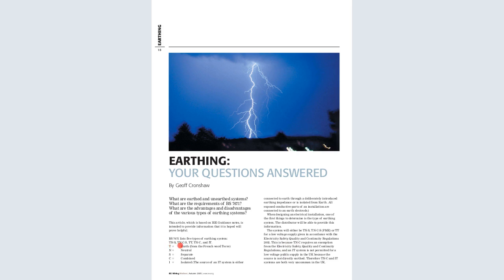So the TNS, TNCS, the TT, the TNC, and the IT system. The T means the earth, from the French word, the N is the neutral, the S is separate, C is combined, and I is isolated. So TNS means that the earth and neutral are separate. The TNCS means that the earth and neutral are combined in part and separate in part. The TT means that the earth and neutral are separate. The TNC means that the earth and the neutral are combined, and the IT means that it has an isolated earthing.